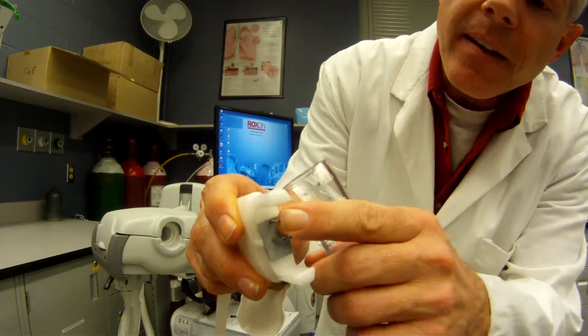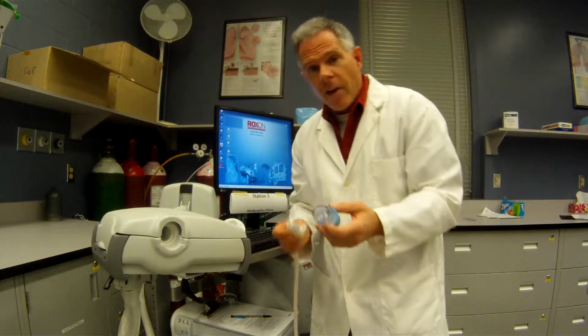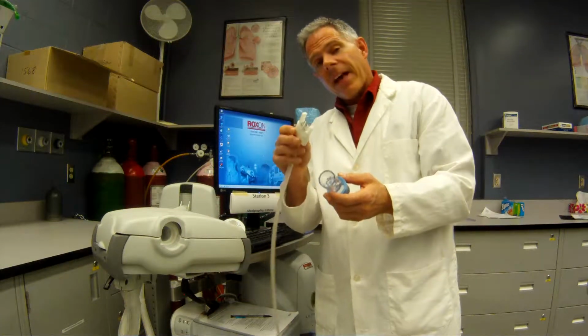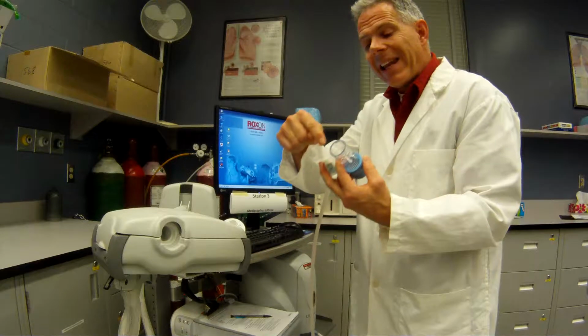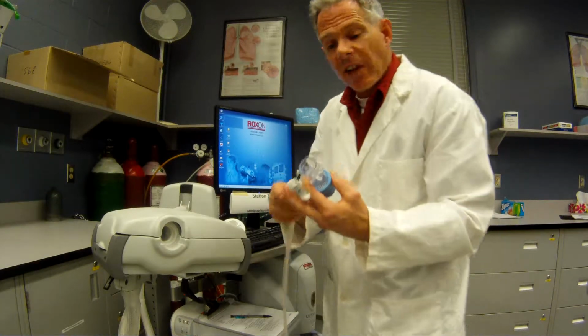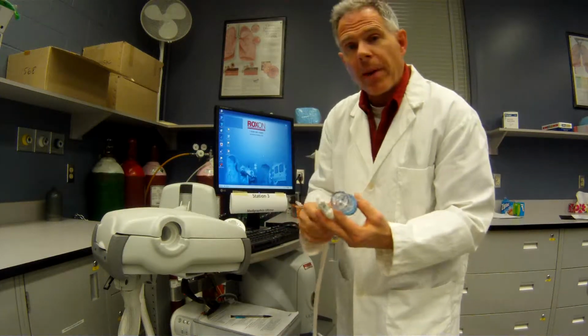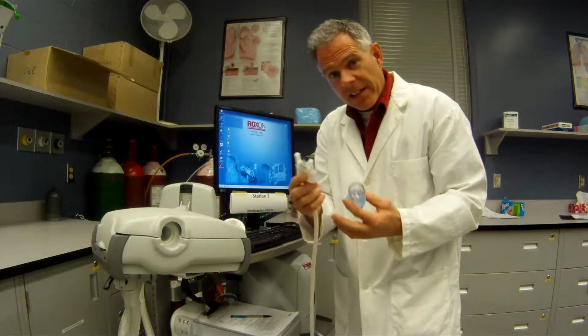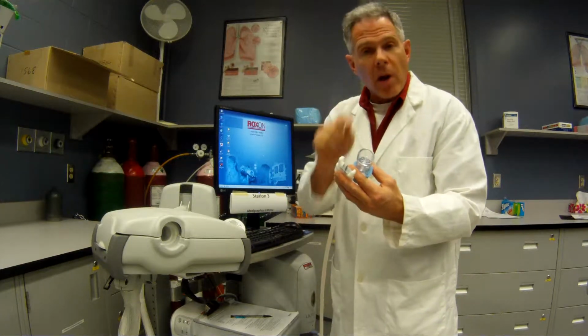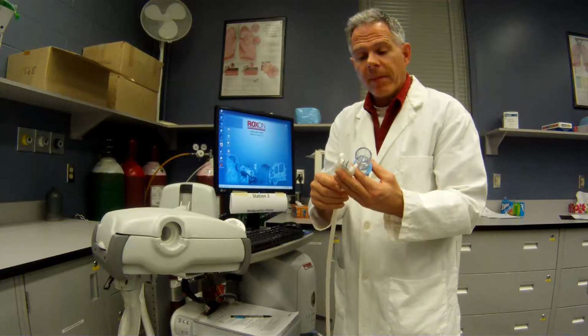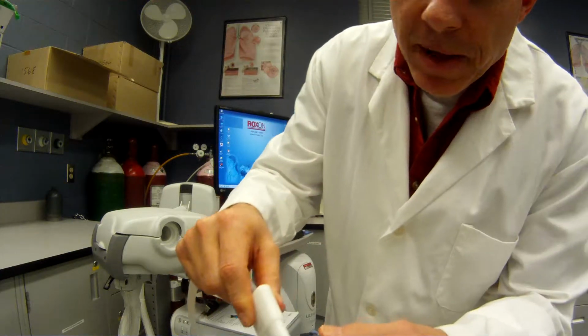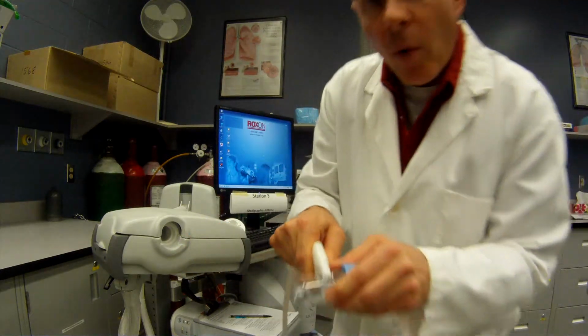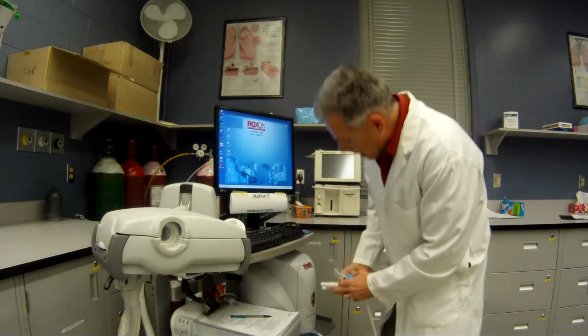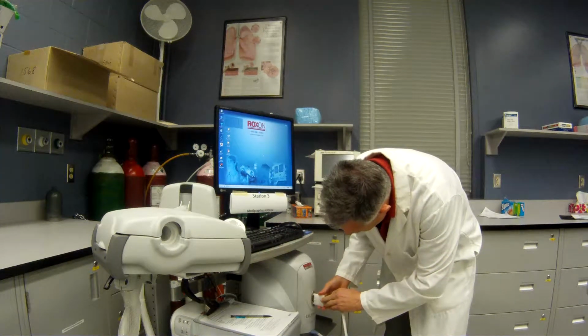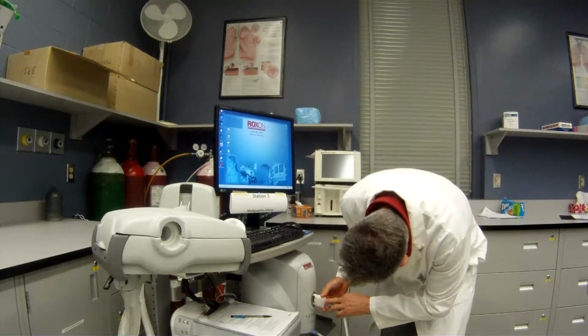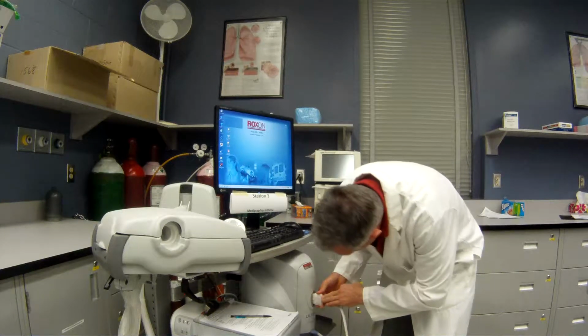This third part here, this other little tiny tube here, is for our gas analyzer, and that's hooked up back up into here so it can analyze the amount of oxygen or carbon dioxide that is being exhaled by your patient. And for very special tests like the DLCO, it'd be measuring carbon monoxide levels as well and helium. So be sure you hook that up correctly. Now, when we're doing a gas calibration, we're going to hook it up just like this to this gas analyzer unit. Be very careful making sure that those line up correctly.